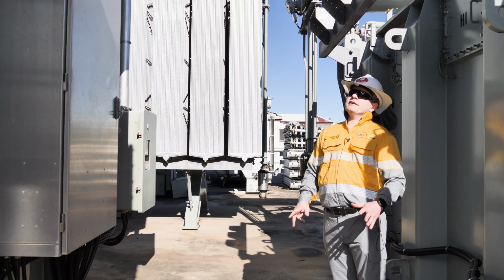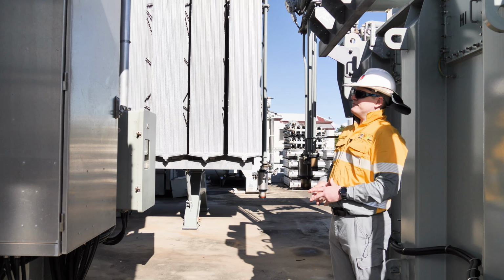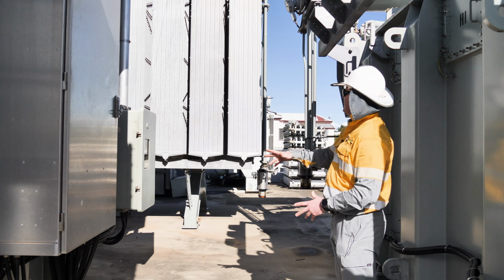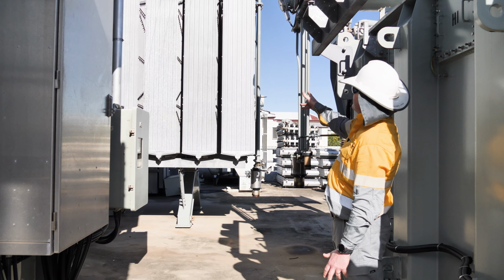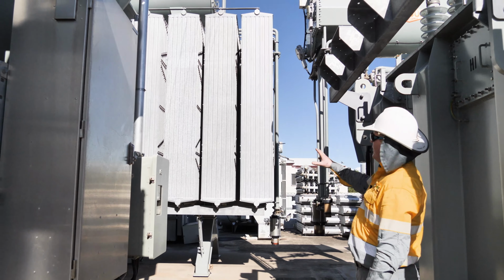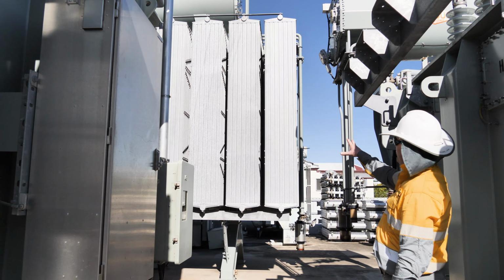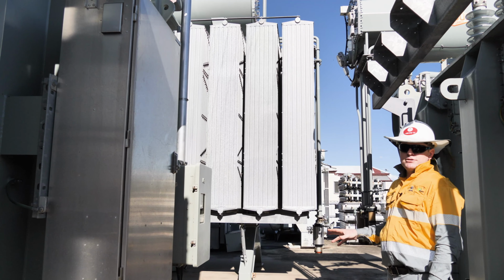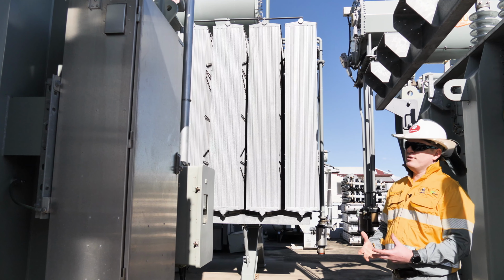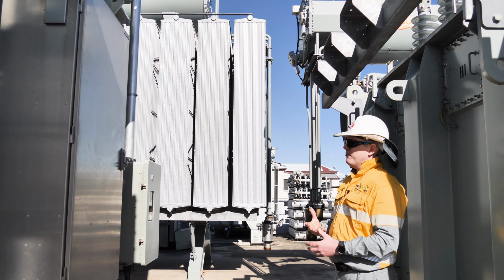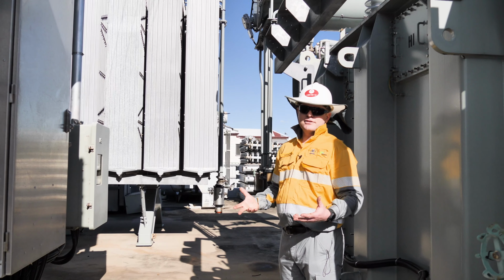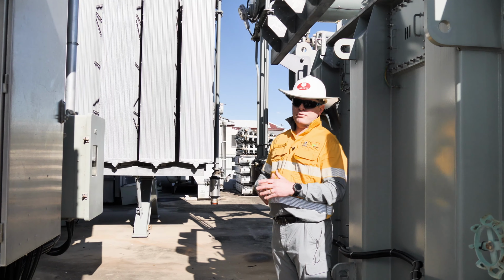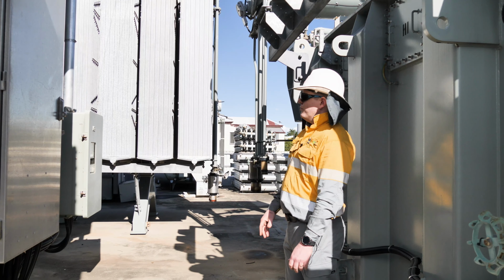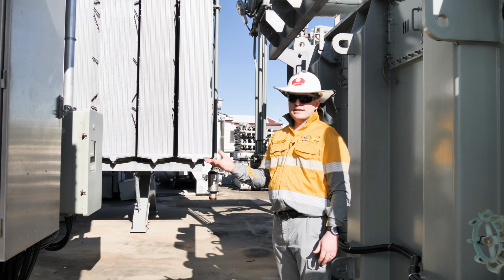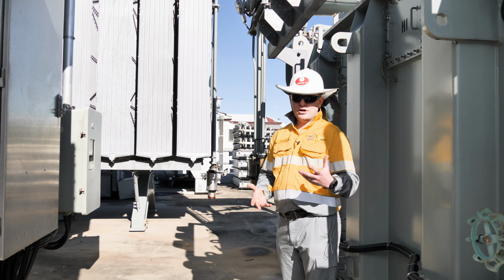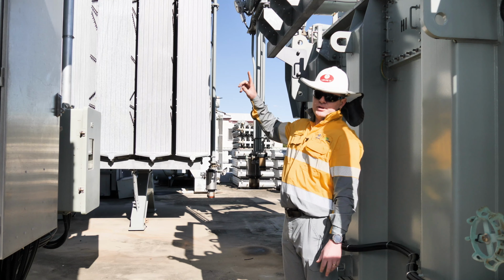Alright, so now we're a little bit closer to this large 100 MVA Wilson transformer, and one of the really noticeable features are the fins on the radiator. So this is an oil-filled transformer, and the purpose of these fins is to cool the oil. The thing that really damages transformers is heat. Heat in the transformer can damage the insulation around the windings, and the purpose of the oil is to not only electrically insulate the transformer and its components, but also to keep it at a safe temperature so we don't damage it. The way this particular transformer operates is it has forced cooling, so it's OF, and there's a pump that helps circulate the oil.